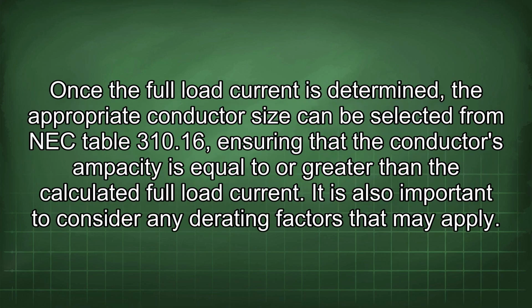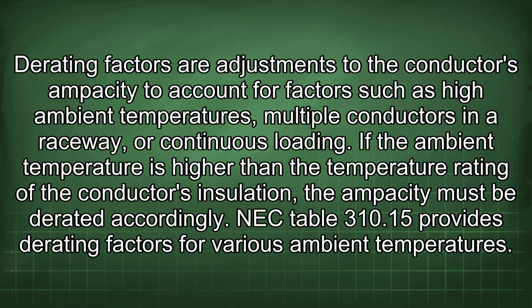Once the full load current is determined, the appropriate conductor size can be selected from NEC Table 310.16, ensuring that the conductor's ampacity is equal to or greater than the calculated full load current. It is also important to consider any derating factors that may apply. Derating factors are adjustments to the conductor's ampacity to account for factors such as high ambient temperatures, multiple conductors in a raceway, or continuous loading.